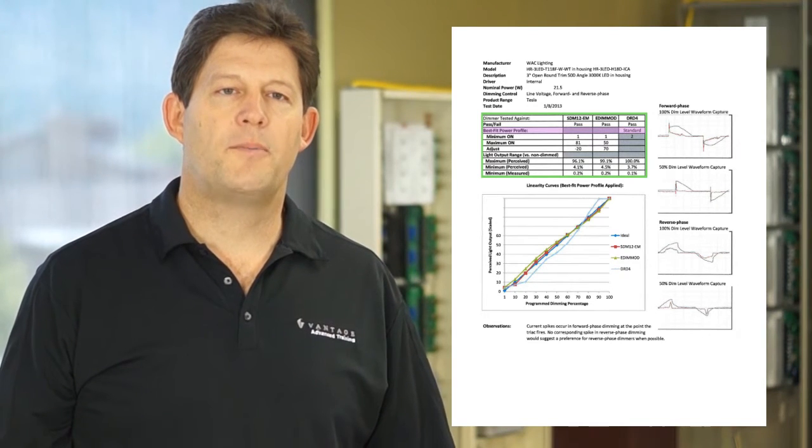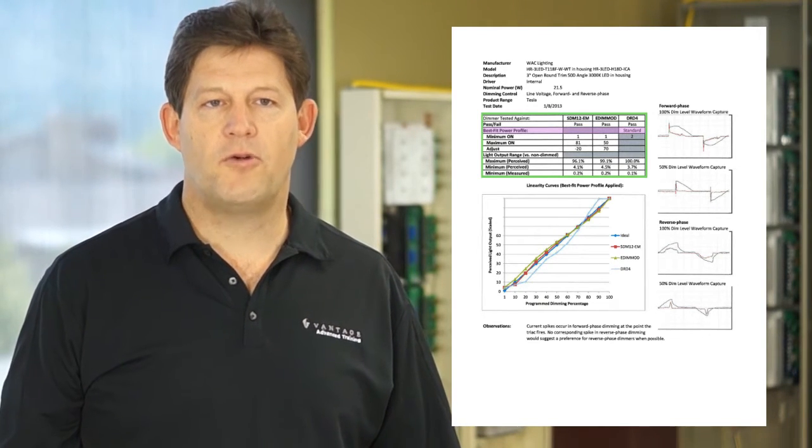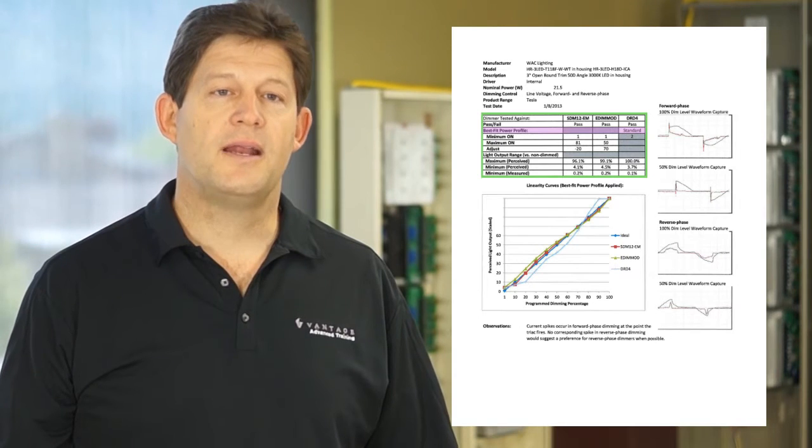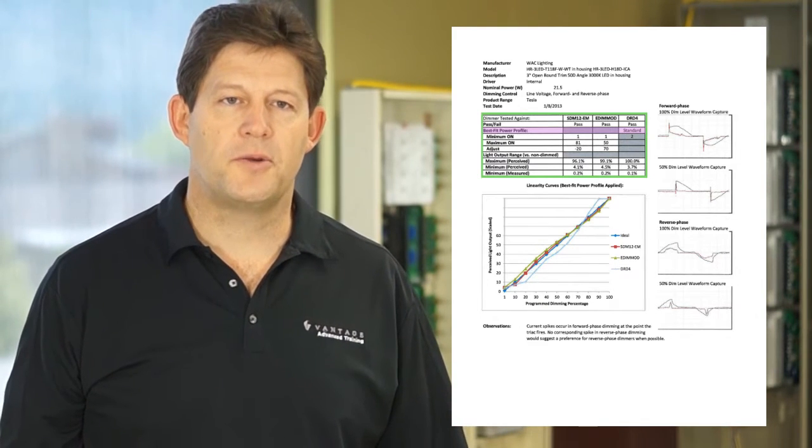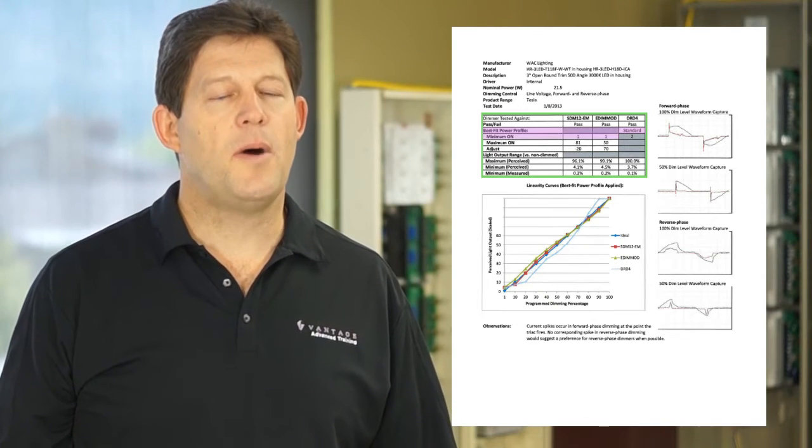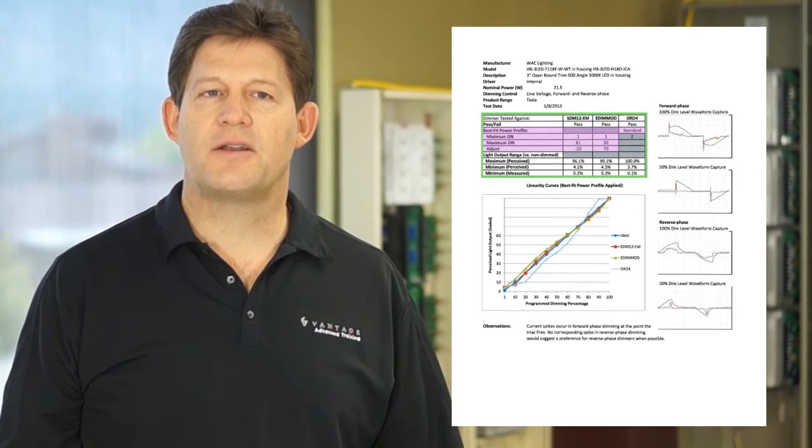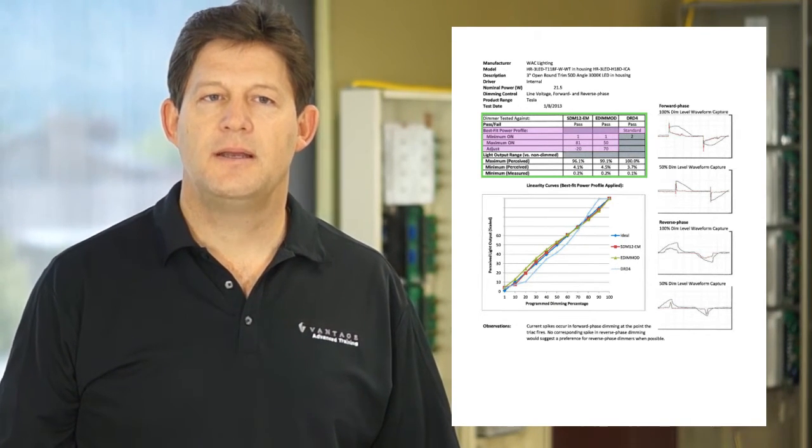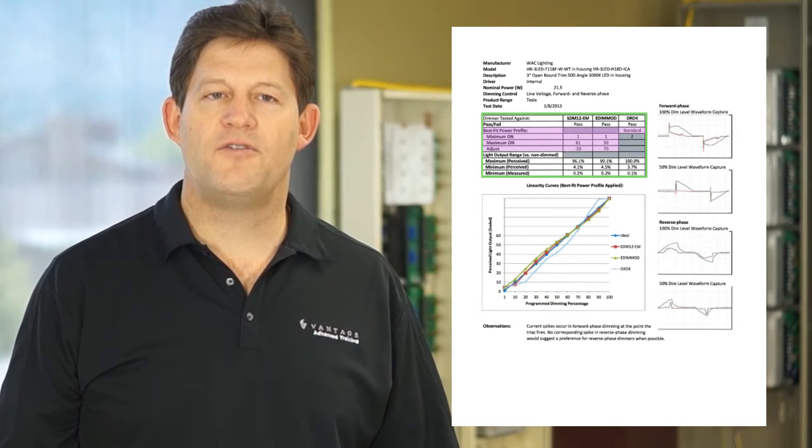Next you'll find the power profile parameter values that give best performance. We'll illustrate in a moment how to apply these parameters on your project. While we can vary minimum on, maximum on, and adjust factor for the native Vantage dimmers, these are not variable with the DRD4.